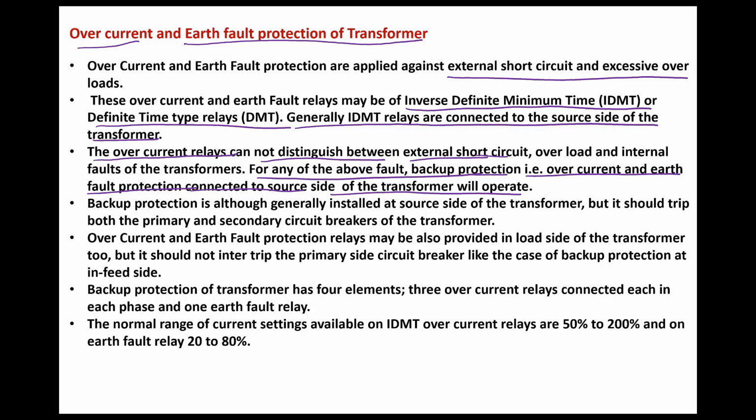Apart from this, inside the transformer we have a differential protection. So all these three relays are incorporated to take care of the internal faults of the transformer. If external faults like short circuit or overload occur, then to take care of them we use the overcurrent relays. But the relay doesn't know whether the fault is inside or outside the transformer. Whenever the current exceeds the pickup value, it will trip.